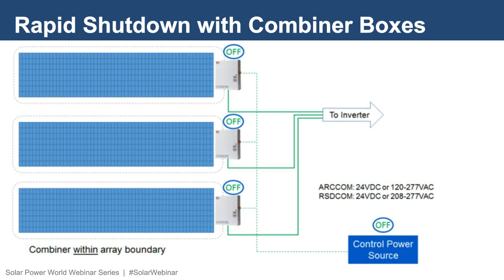The DC output circuits transmitted from the array to the inverters are now de-energized. Additionally, the RSDCOM will bleed any inverter capacitance that may be on those output circuits, being held by the inverter's capacitors if they're not able to naturally discharge within the allotted time frame defined by the National Electric Code.